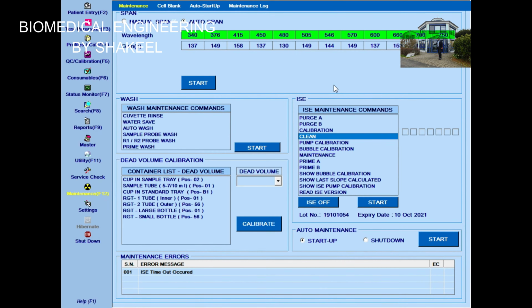Let's start from ISE. So this is purge A. This is used to purge calibrant A solution through the tubing from the reagent module to the ISE module. Purge B. This is used to purge calibrant B solution through the tubing from the reagent module to the ISE module. This is the calibration for sodium, potassium and chloride.